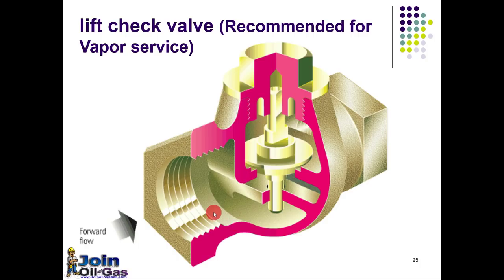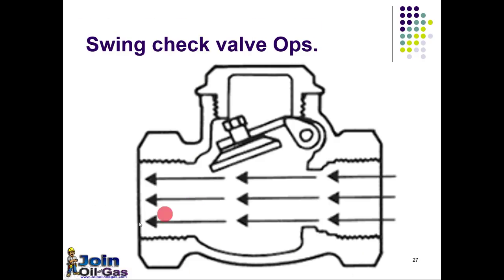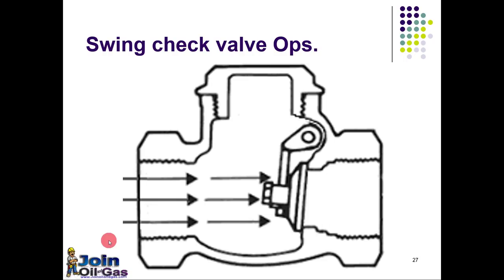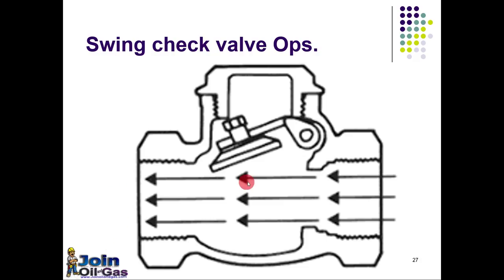Another type is the lift check valve. The flow inlet — when there is enough pressure it will lift the check valve and the flow will go to the outlet section. Whenever the flow tries to come back, this disc will close. There is also the swing check valve, mostly used for liquids. Flow enters from one side, lifts the swing plate, and the flow moves forward. Whenever the flow tries to reverse back, the flapper closes and stops the backflow.